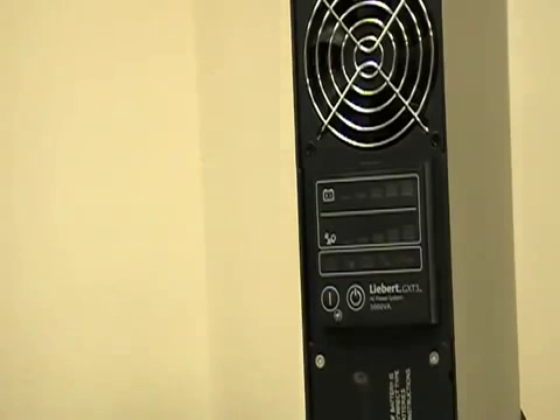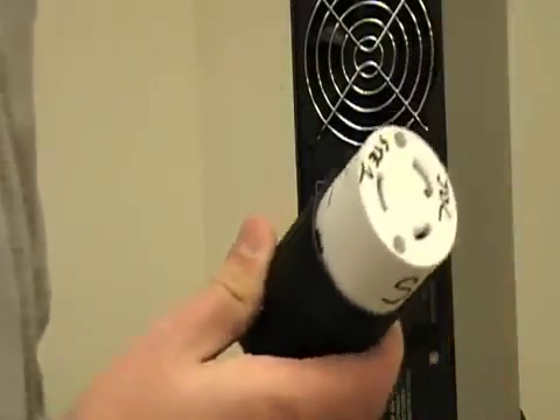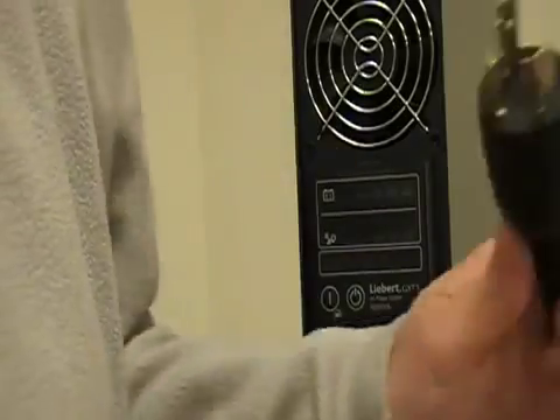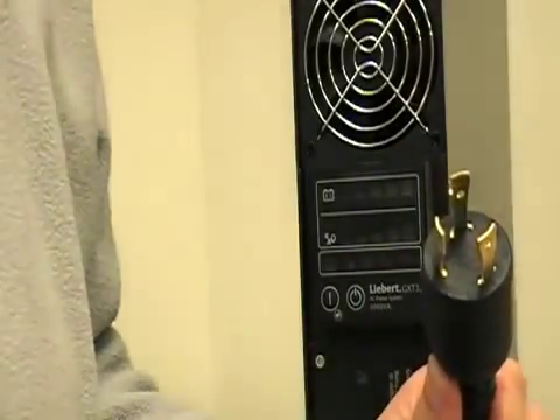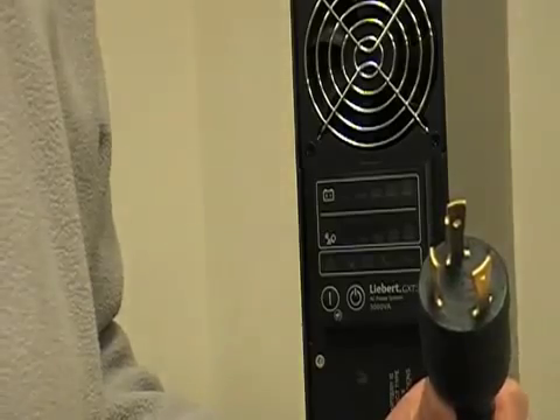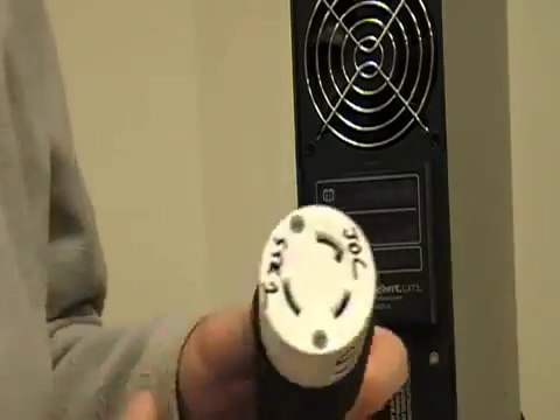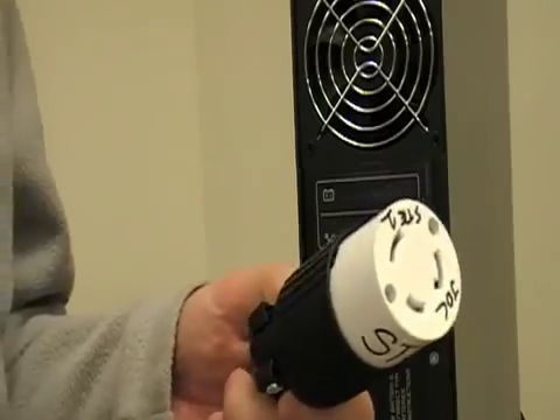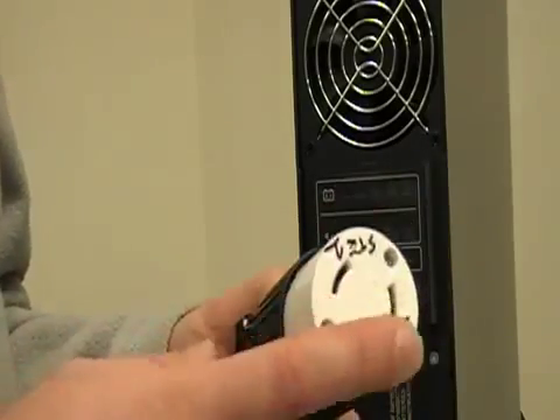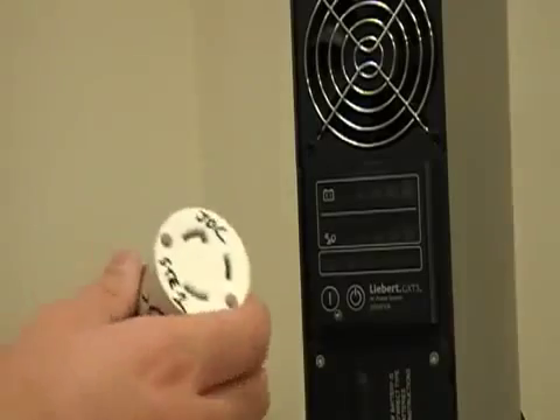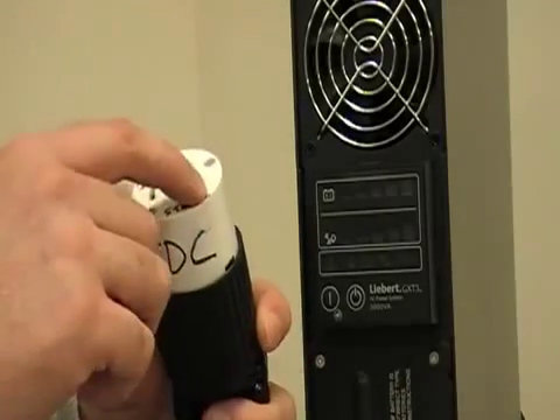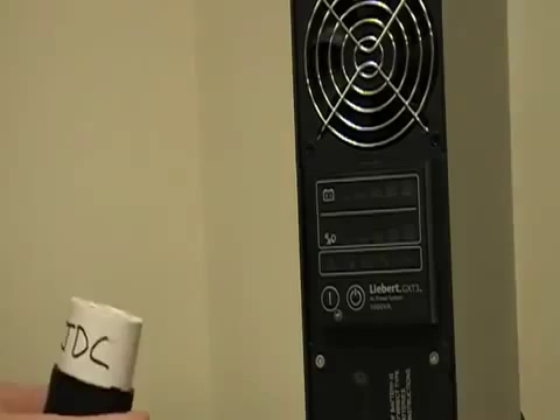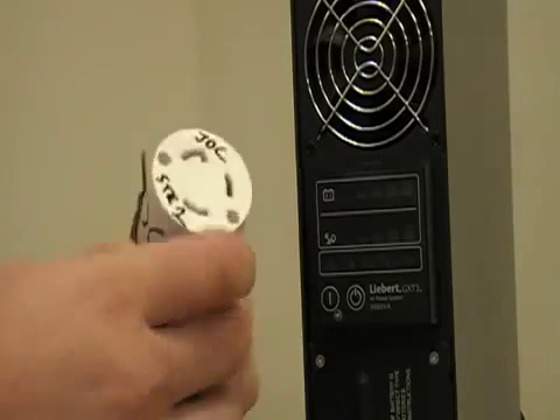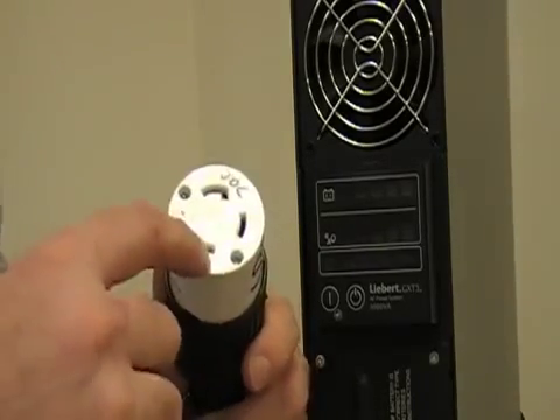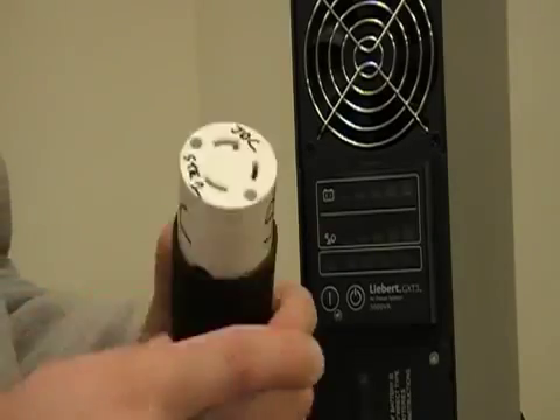Basically, before we put power to the unit, right here we have an L5-30R receptacle, and that's going to plug into the power cord, which is on the back of the unit, which is an L5-30P plug. Prior to turning the unit on or plugging it in, we need to verify that this plug is oriented properly for the polarity of your line and your neutral. The plug that has the little prong on it is your ground. The larger blade is the hot. The smallest blade is the neutral.